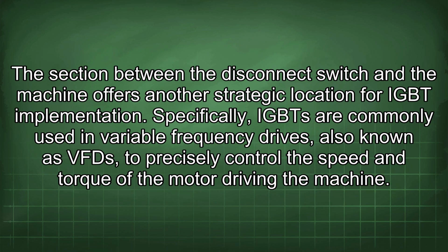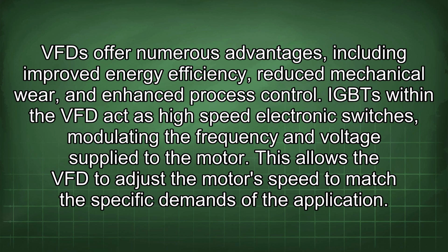The section between the disconnect switch and the machine offers another strategic location for IGBT implementation. Specifically, IGBTs are commonly used in variable frequency drives, also known as VFDs, to precisely control the speed and torque of the motor driving the machine. VFDs offer numerous advantages, including improved energy efficiency, reduced mechanical wear, and enhanced process control. IGBTs within the VFD act as high-speed electronic switches, modulating the frequency and voltage supplied to the motor. This allows the VFD to adjust the motor's speed to match the specific demands of the application.